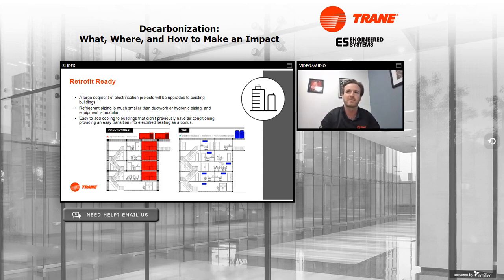Another side bonus: a lot of projects we see these days, especially in the north, are schools, where you're adding cooling to buildings that never had it before, because they want to use the spaces in summer for programs. If you install a VRF system, which can both heat and cool, you get the cooling they want while also walking them into electrified heating, since the system can heat as well. Another benefit of VRF is you can use the controls to connect to a backup heat source, so you could use VRF heating in mild conditions, but once it gets below, say, 20 degrees and it's really cold out, you can still fall back on your existing boiler system.